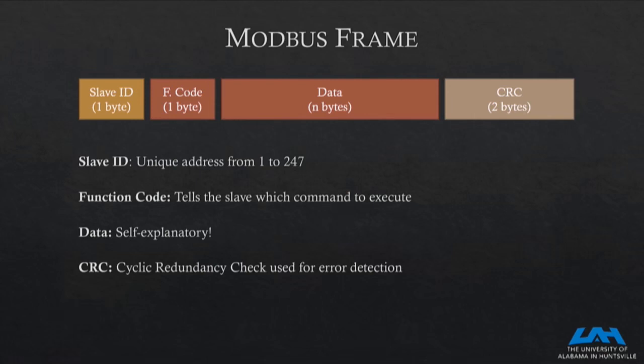The slave ID is a unique address because it was based on serial networks, so you have to have a way to address a device. The function code is what I was talking about. It tells the slave device what to do, like the command it should obey. The function code varies from reading or writing to more memory areas.